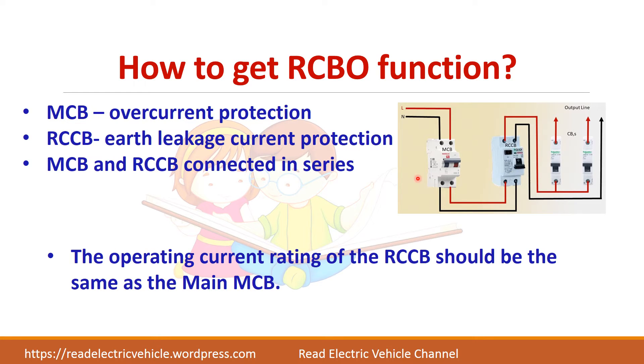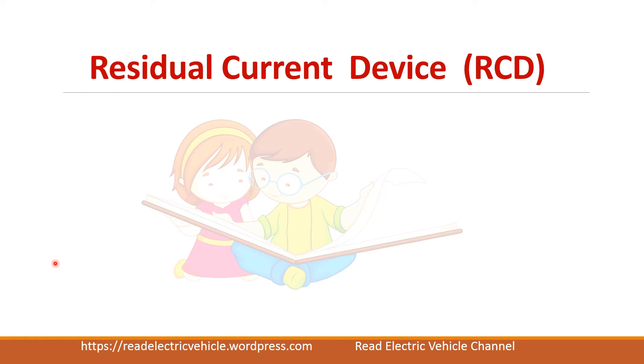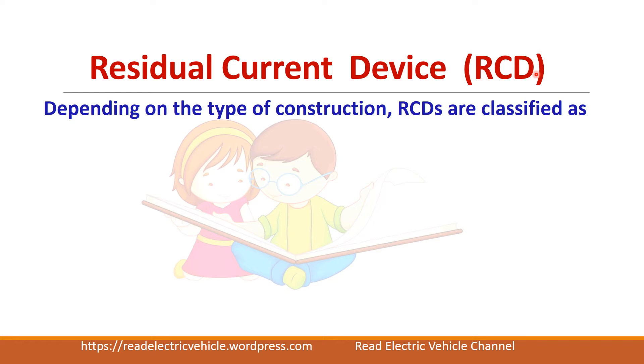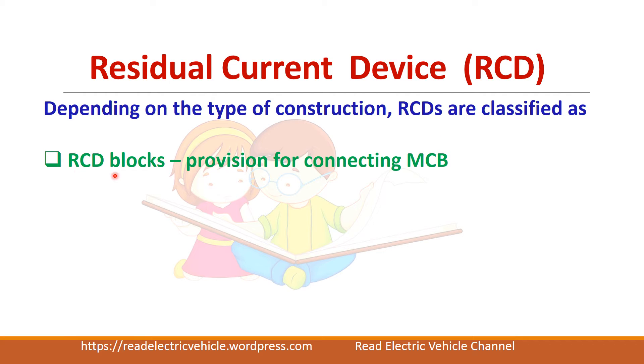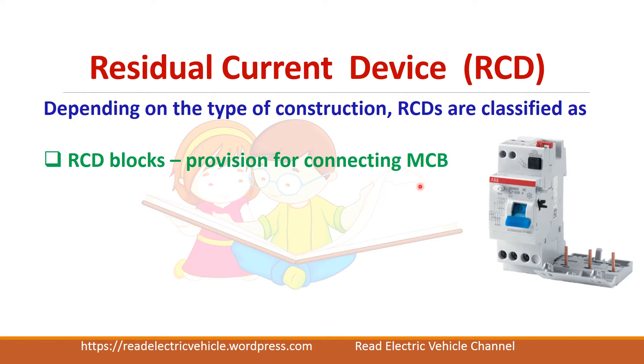The only thing is that we have to ensure that the current ratings of both devices should match. The devices used to detect residual current are called RCD devices. Depending upon the type of construction, RCDs are classified as RCD blocks, which have the provision for connecting the MCB. You can see it is a RCCB with an extension part where you can connect an MCB. Depending upon the current rating, you can choose a compatible MCB and use it as a single block.